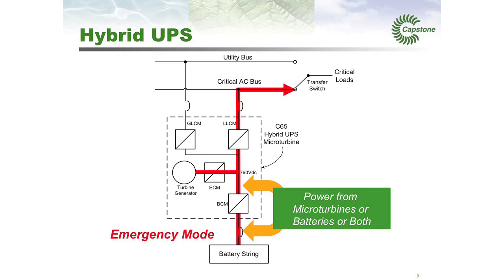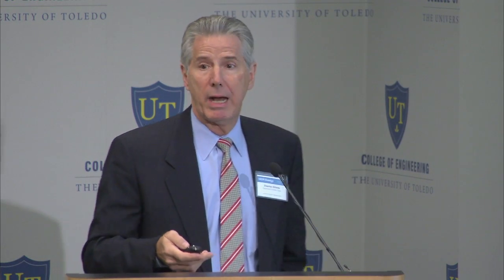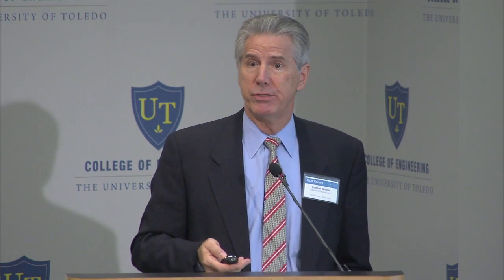That gives you flexibility to maximize efficiency and therefore the economics of running the system. And of course, if the utility goes away, we provide the backup. If the microturbine isn't already running, we take energy from the battery to start the turbine, and in the meantime the battery also powers the critical loads, so there's no interruption under any of these scenarios. That gives us a high reliability, high availability, high efficiency solution.